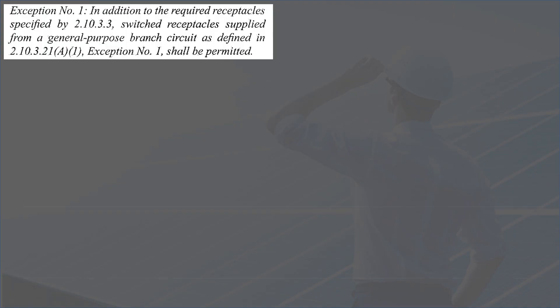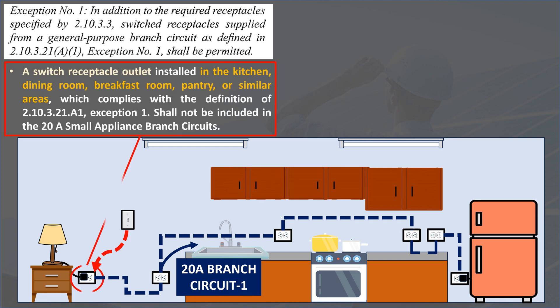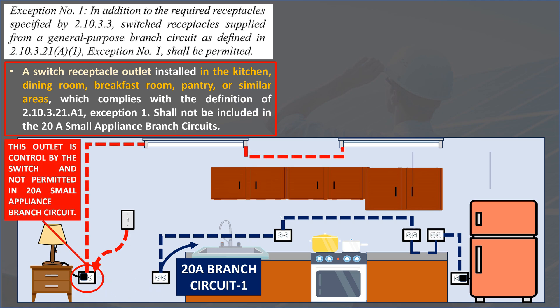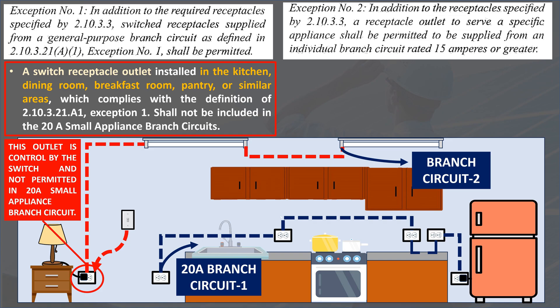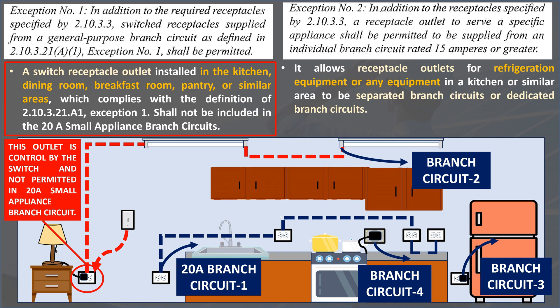How about the other kitchen — can we combine those outlets with the other kitchen outlets? For Exception 1, if a switch receptacle outlet is in the kitchen, dining room, breakfast room, pantry, or similar area that complies with the definition of 2.10.3.21A, it is not permitted to be included in 20A small appliance branch circuits of kitchen and countertop outlets. For Exception 2, it allows receptacle outlets for refrigeration equipment or any equipment in a kitchen or similar area to be on separate branch circuits or dedicated branch circuits. The rating should be 15A or larger, depending on the rating of the equipment it serves.